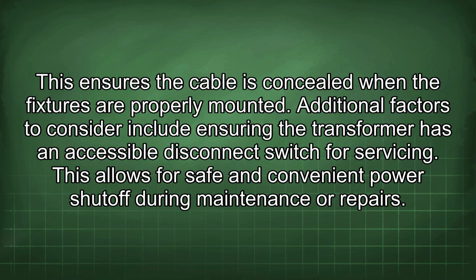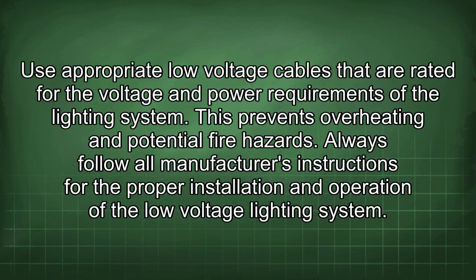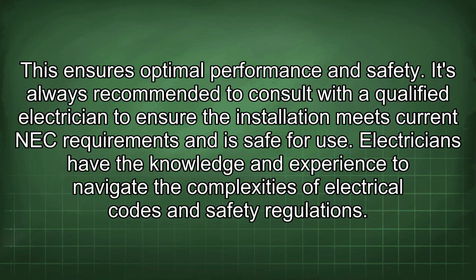Additional factors to consider include ensuring the transformer has an accessible disconnect switch for servicing. This allows for safe and convenient power shutoff during maintenance or repairs. Use appropriate low-voltage cables that are rated for the voltage and power requirements of the lighting system. This prevents overheating and potential fire hazards. Always follow all manufacturers' instructions for the proper installation and operation of the low-voltage lighting system. This ensures optimal performance and safety. It's always recommended to consult with a qualified electrician to ensure the installation meets current NEC requirements and is safe for use. Electricians have the knowledge and experience to navigate the complexities of electrical codes and safety regulations.